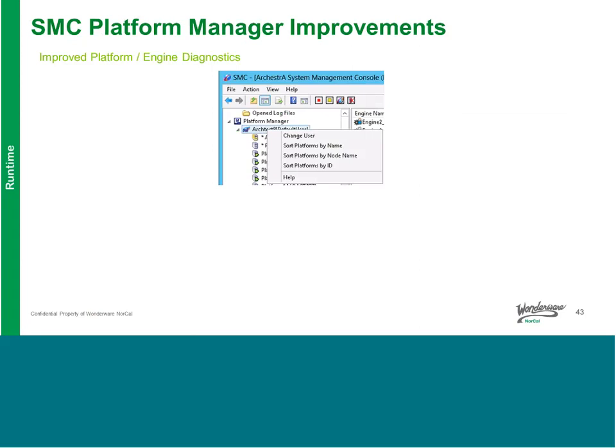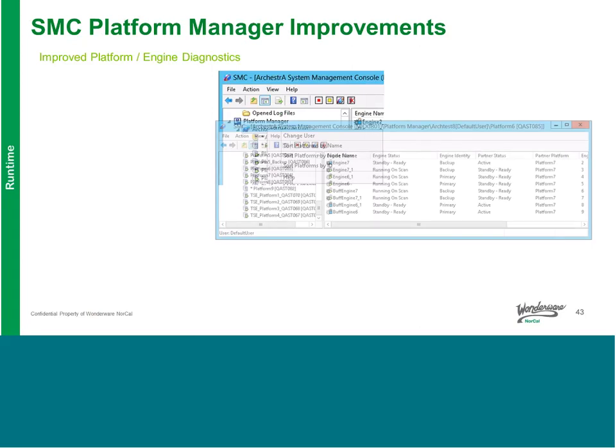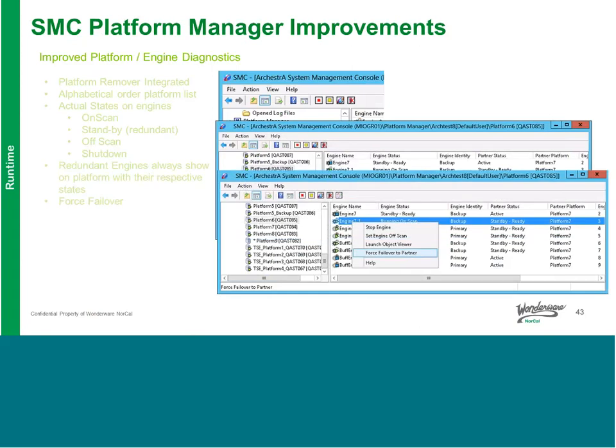Inside of the System Management Console, we have improved platform and engine diagnostics so that you can really do things that you previously had to go into the IDE for. So platform remover, actual states of engines, are they on scan, off scan? Redundant engines show which platform they're running on. You can force failover directly from the System Management Console. So a lot of things that you had to do programmatically before is now built right into the System Management Console.